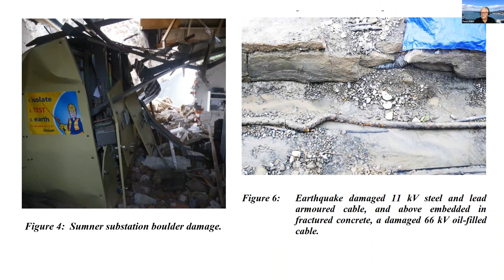The substation was basically destroyed, and cables were damaged underground. The same happened to other infrastructure like sewerage pipes and water pipes. PVC pipes tended to shear through at the T-junctions, whereas PE pipes apparently got stretched and popped out of the ground. So one must include that in your design, but you can never cope with everything nature can throw at you.